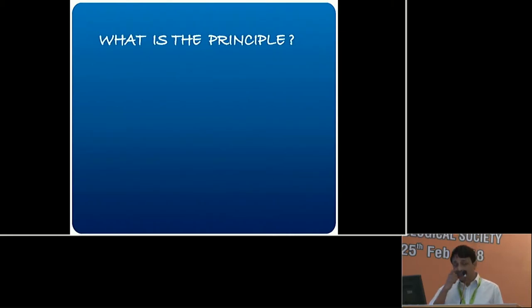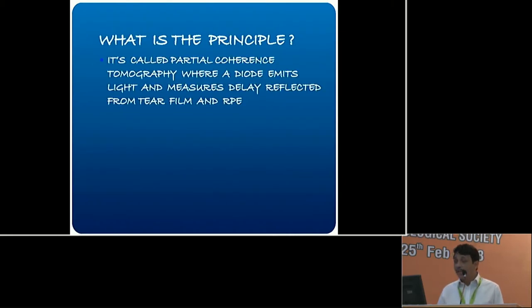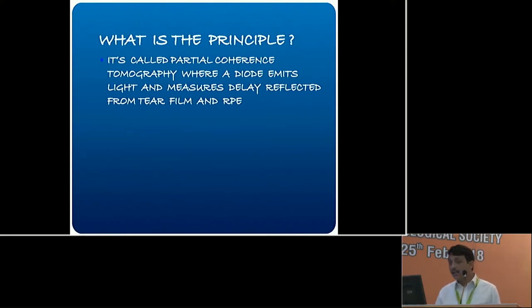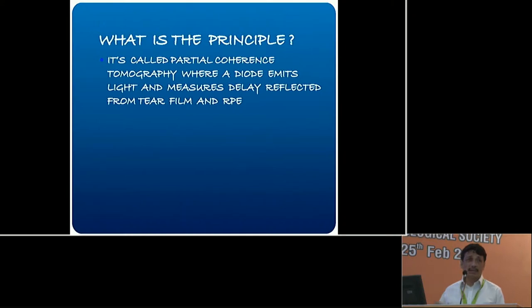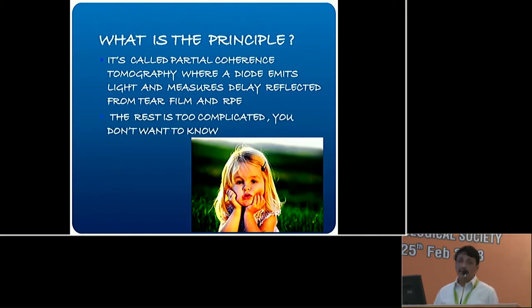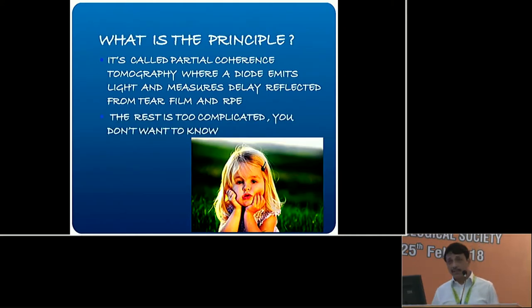Now what is the principle? The principle is called partial coherence tomography, where a diode emits light and measures the delay reflected from the tear film and RPE, and calculates from the difference in interference patterns between what was sent and what was reflected. From that difference in interference patterns, it calculates the axial length. The rest is too complicated — this is not a physics lecture.